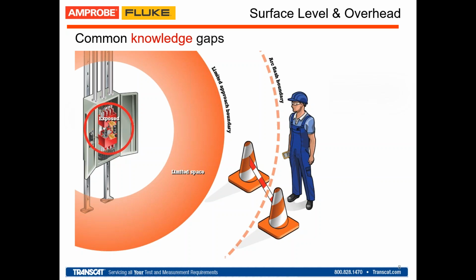And at this point, experienced users need to wear PPE, and they should be qualified workers. Qualified workers means, number one, that they know the safe distances defined by the company and by OSHA. Number two, they have the right PPE. Number three, they know how to operate contact voltage or current detectors, test and measurement tools, or non-contact tools. And it is highly recommended that non-experienced users or technicians should not get to the limited approach boundary, even if they have PPE gear.